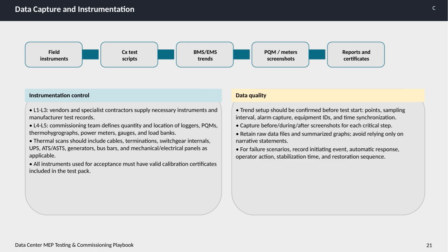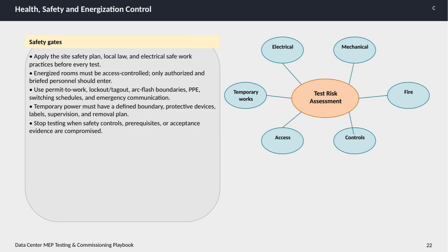On this slide, we focus on health, safety, and energization controls during data center MEP testing and commissioning. Safety is paramount. So before every test, it's essential to follow the site's safety plan, comply with local laws, and adhere to electrical safe work practices. When dealing with energized rooms, restrict access strictly to authorized and briefed personnel to minimize risk. Utilize key safety measures such as permit-to-work systems, lockout/tagout procedures, arc flash boundaries, appropriate personal protective equipment, detailed switching schedules, and ensure clear emergency communication is in place.